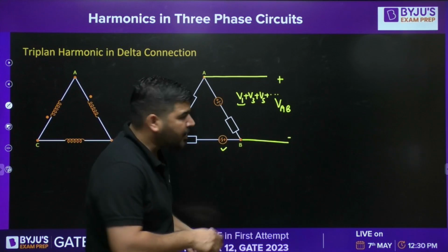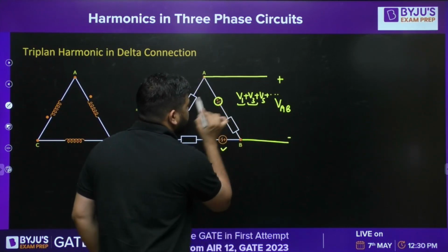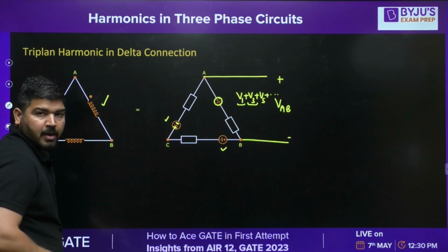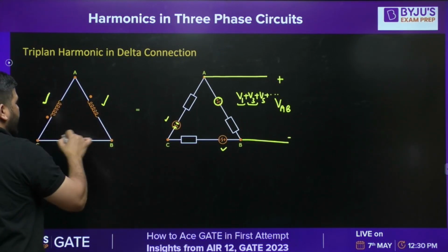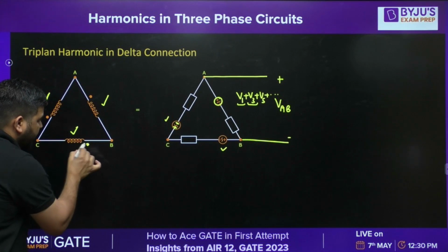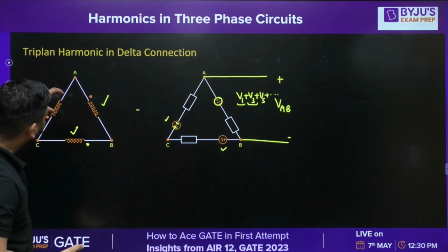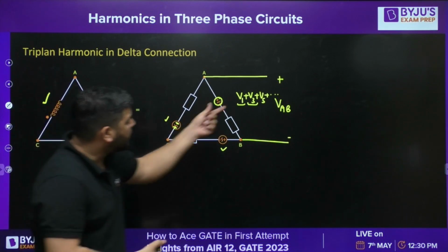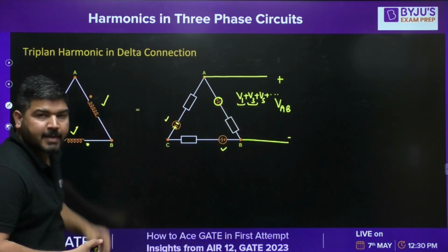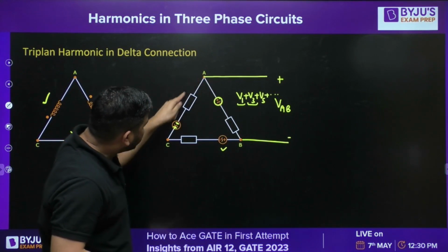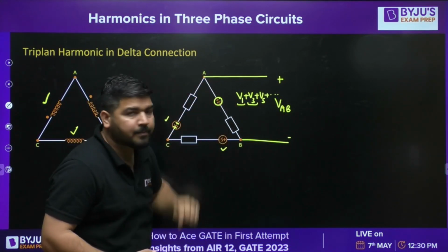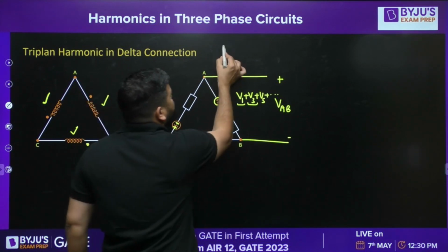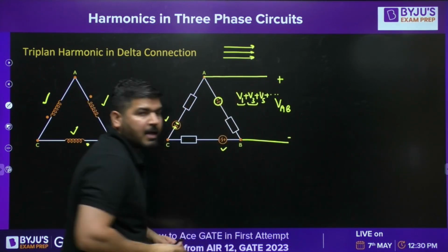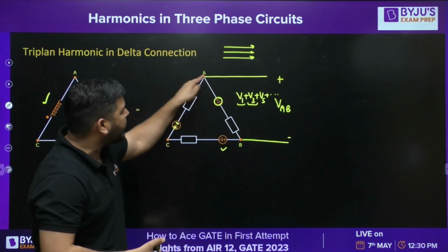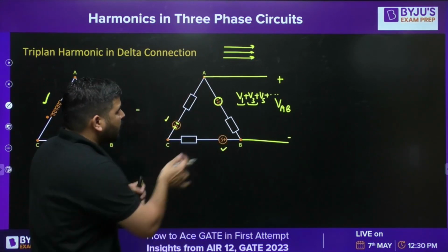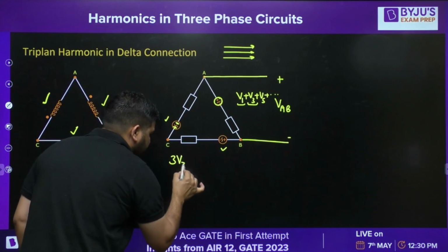But because of the third harmonic component, if you look at the third harmonic voltage of this coil and of this coil, and this coil—because there are three coils—if you take the third harmonic voltage in these three coils, they will be in the same phase. And if you move in a loop, you can see they will be added. Because they are in the same phase, if you are moving in a loop, they will be added, and the total loop voltage will be 3V3.